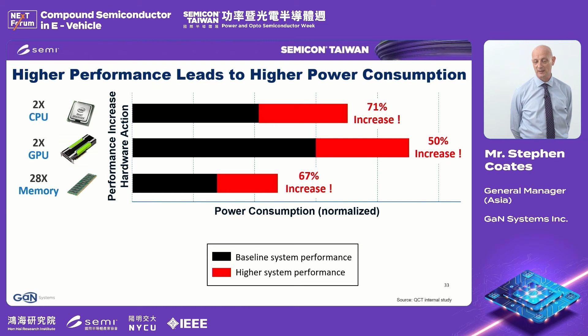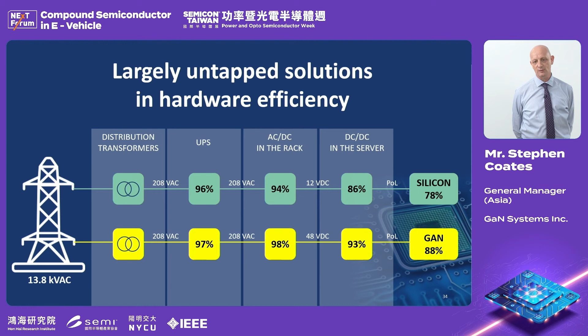Energy efficiency and density can be gained in three areas. Number one, in the UPS, where high voltage is converted and brought into the building. Here I show a large centralized unit, but the evolution is underway to make smaller decentralized units for risk mitigation. Number two, in the rack power supply, at the server rack where AC is converted to DC. And lastly, the individual server power supplies, where the DC is converted to low voltage DC on the server board.